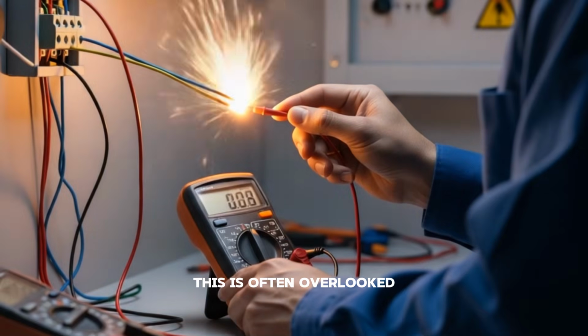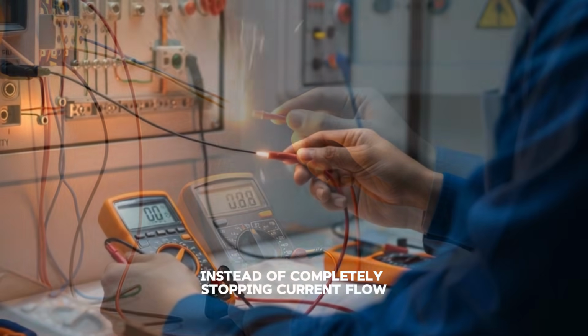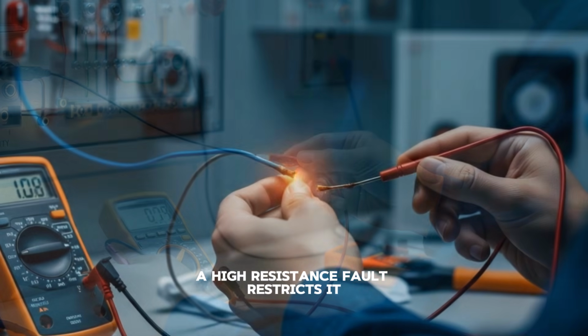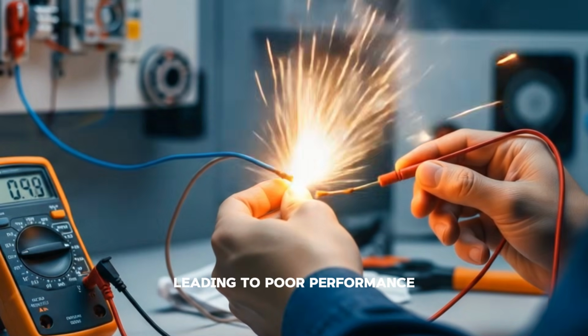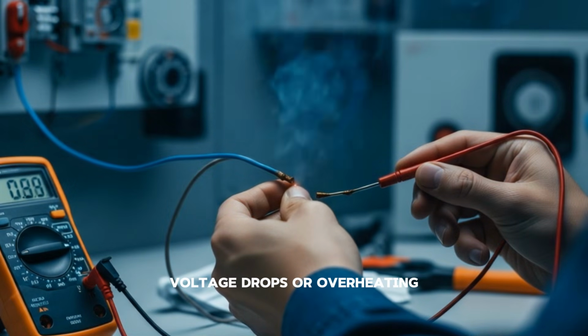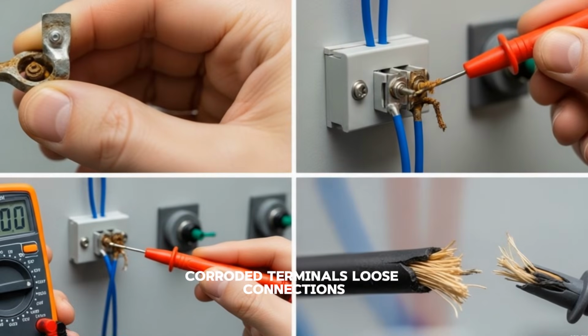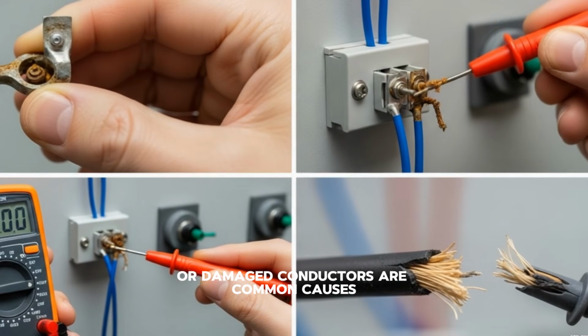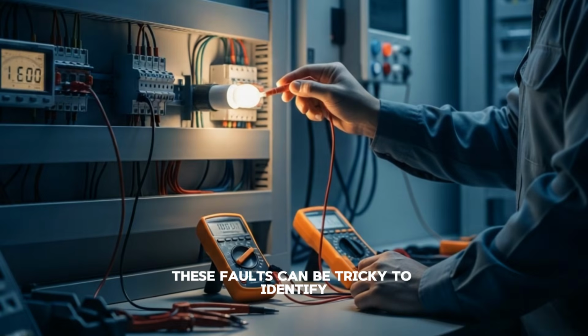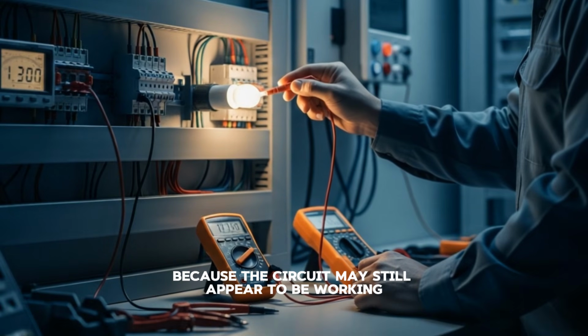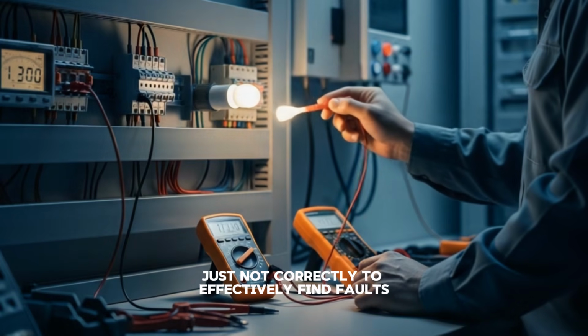Another type of fault is a high resistance connection. This is often overlooked but can cause significant issues. Instead of completely stopping current flow, a high resistance fault restricts it, leading to poor performance, voltage drops, or overheating. Corroded terminals, loose connections, or damaged conductors are common causes. These faults can be tricky to identify because the circuit may still appear to be working, just not correctly.